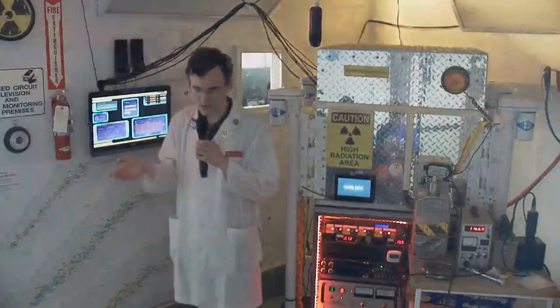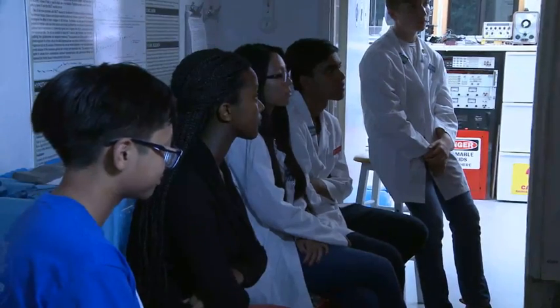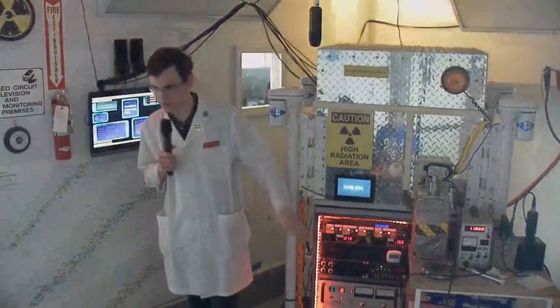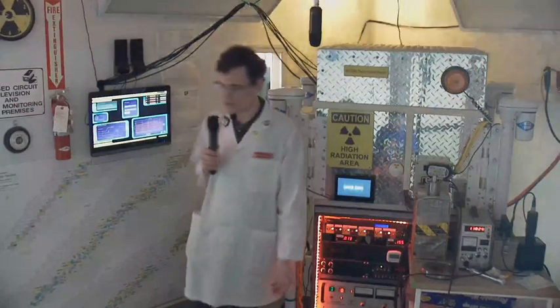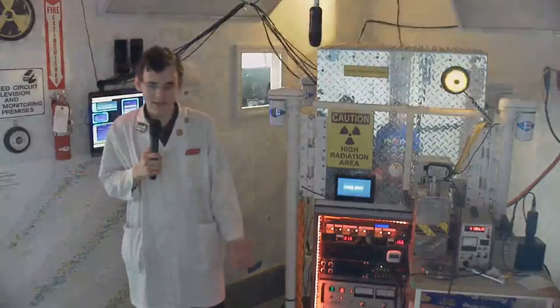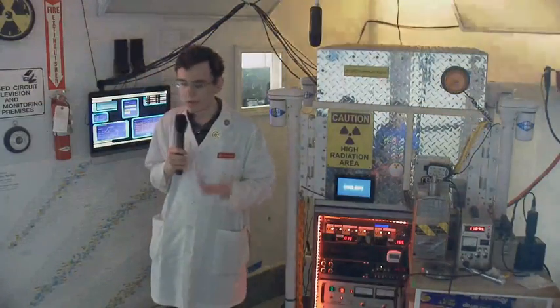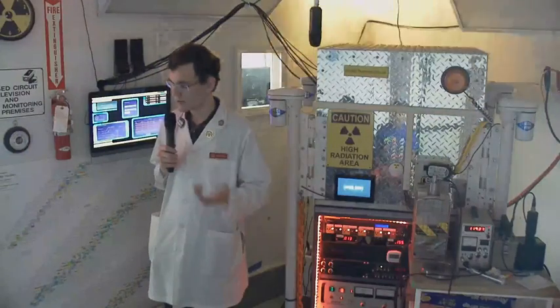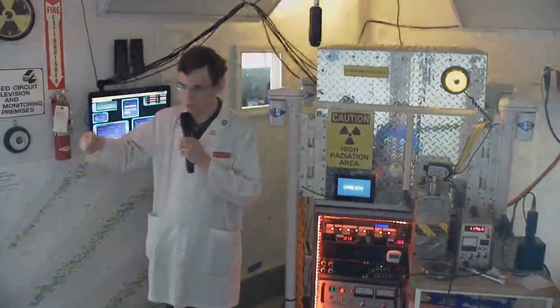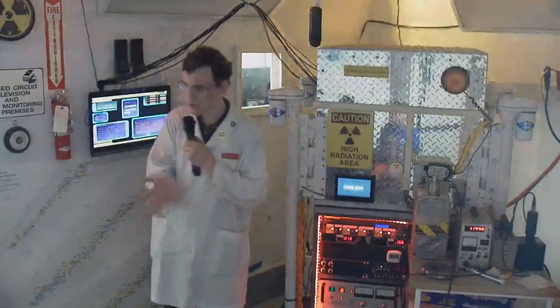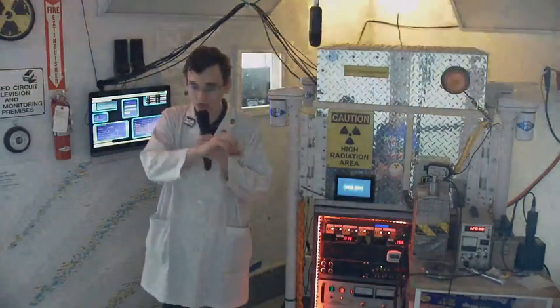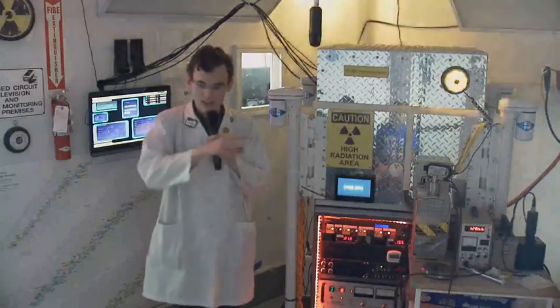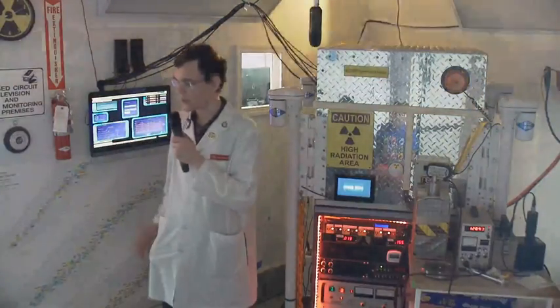Now, the helium-3 tube is interesting. Remember I was talking about the energy levels of the neutrons earlier? How you can have the 2.4 MeV neutrons that come off of it, and you thermalize them and change the energy level. Well, the 2.4 MeV neutron only comes off of the deuterium to deuterium reaction. There are different energy levels of neutrons that come off of different nuclear reactions, and a different energy level of neutron interacts with those helium-3 detectors differently. A higher energy neutron will have a different interaction with the detector than a lower energy neutron. You can record those different interactions and actually create a spectrum of the energies coming off of a reaction.